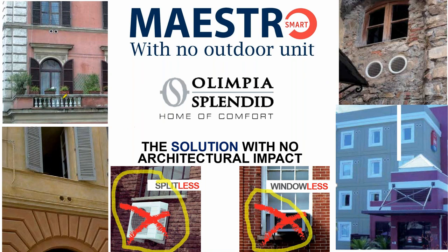And as you can see, it can be installed in the, let's look at the upper right-hand picture. This is the only thing you see on the outside wall are two 8-inch grills. Now, depending on your application, you might also have a 3/4-inch hole for a drain as well. Although the drain is not required in all cases, and I'll explain that a little bit later. But so this unit was installed, the one that I've currently got circled was installed below a window. So when you look on the next picture, you can see that this has three systems on each floor, and those are installed above the window or high on the wall.